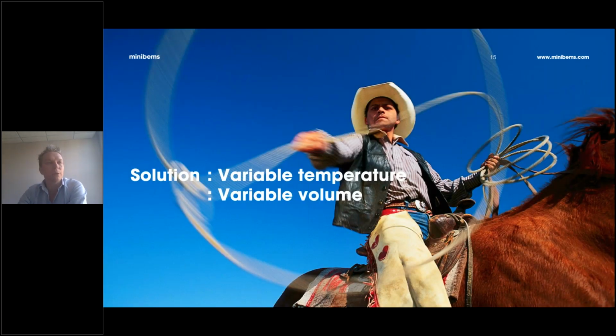So what we aim to do is to deliver a variable temperature, variable volume system, which means that on the primary, as a consequence of the secondary, but on the secondary side of the heat network, so in apartments and in houses, in heat consumers on the heat network, we are variably delivering both temperature and the volume flow rate in order to meet the real-time actual demand of that heat consumer.